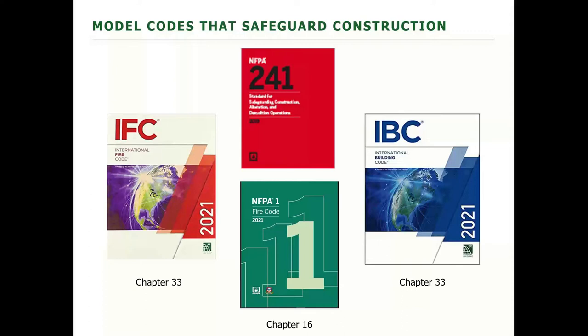So even if you are an NFPA 1 fire code jurisdiction, NFPA 241 would still apply to you if you adopt the IFC, because the IFC in Chapter 33 adopts 241 by reference. It says if there is a requirement in NFPA 241 that is not covered in this code, the requirement in 241 shall apply. And because the IBC references the IFC, which references 241, then it would apply. So there is a legal pathway to compliance if you choose to enforce it.